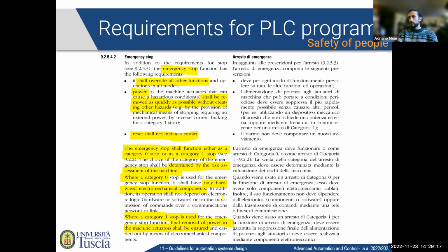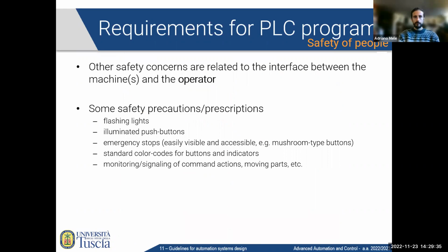Where a category 0 stop is used, only hardwired electromechanical components shall be used, and we have already seen that. When category 1 is used, final removal of power to the machine shall be ensured, but only after the stop has been taken care of. Other safety concerns are related to the interface between the machines and the operator.